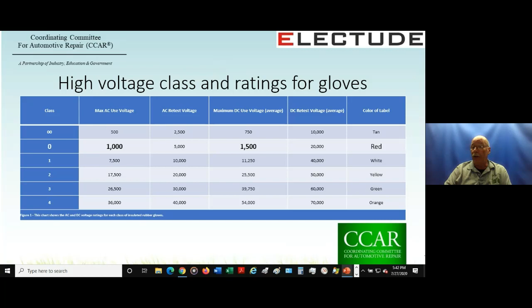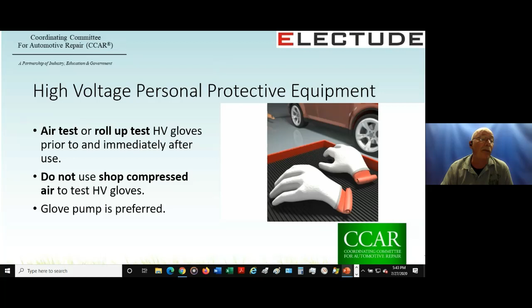So, rubber gloves will need to be inspected for surface defects. Air testing is the standard for integrity, by roll-up testing or using a glove pump. I always recommend a glove pump. Under no circumstances should shop air be used, or allow a student to test them or apply shop air to a glove. Once they do that, that glove is junk, in my opinion. Gloves can be pinholed by overinflation, and a pinhole is sufficient to convey a lethal shock. This all goes back to cost too, because you'll see later in the presentation our example of high voltage gloves that cost us $130 US.